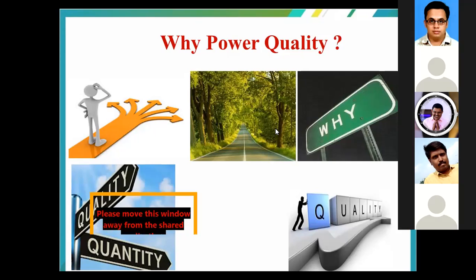Again, if we do not contain it at the generation point, it is going to get transmitted through the transmission line, from where we are going to have the problem with all the grid-connected systems. Again, it may cause circuit breakers or relays to malfunction, which in turn may result in a brownout or blackout of the grid or the electrical networks.